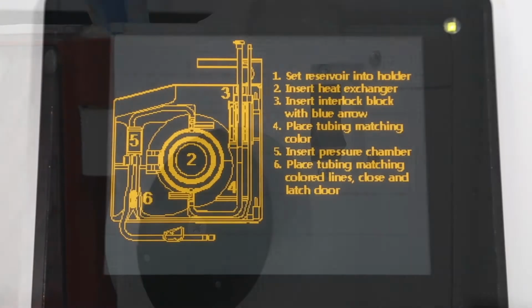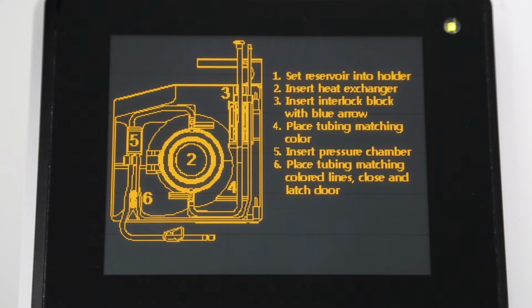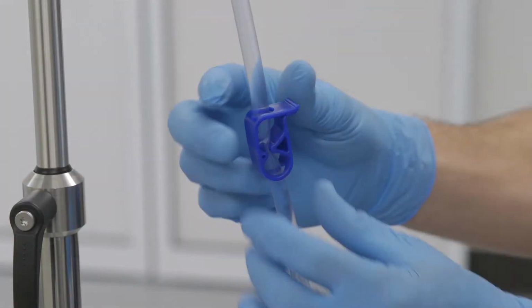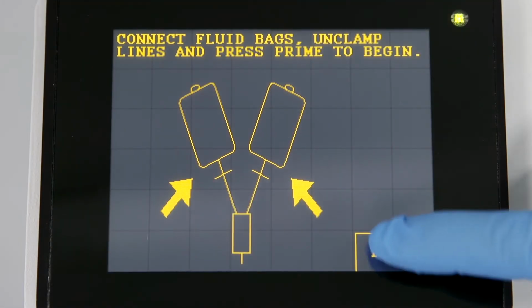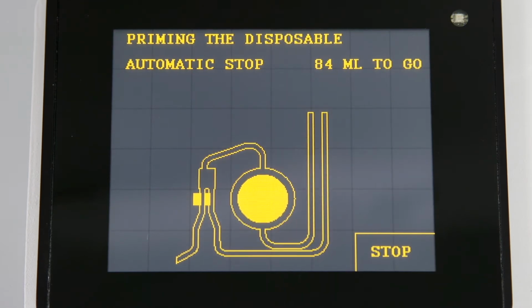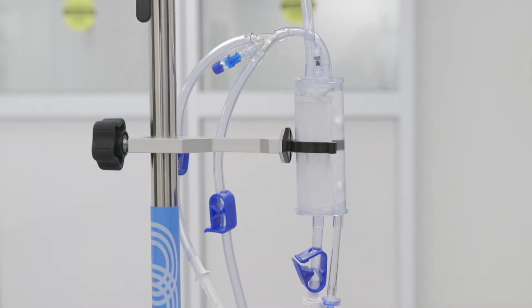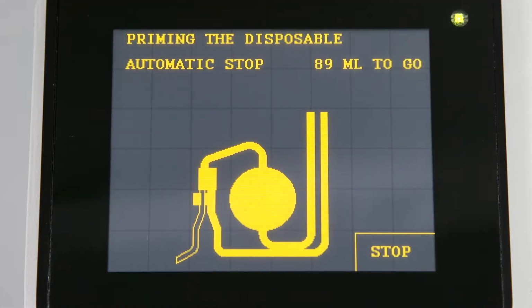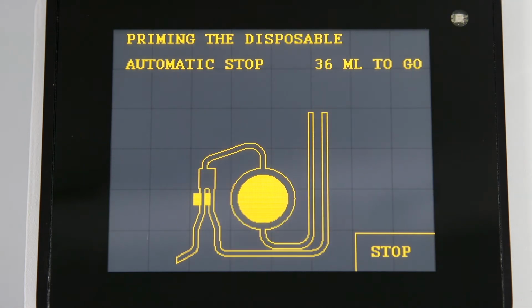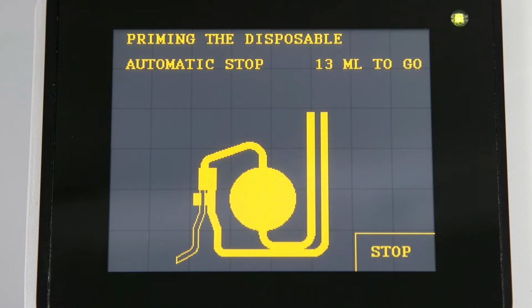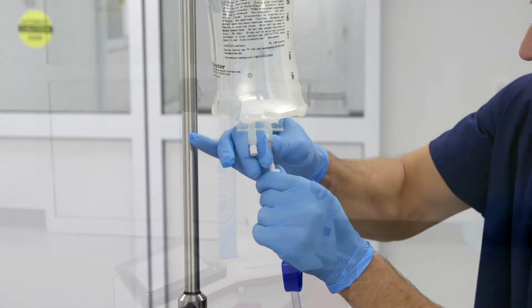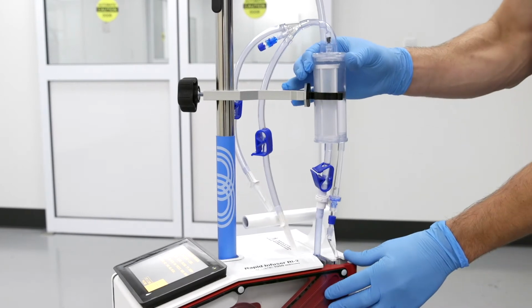When first switched on, the screen will display instructions for installing the disposable set. Press Next to move to the prime screen. You will now be instructed to connect fluid bags and unclamp lines. When ready, press Prime to begin priming the disposable circuit. The roller pump will automatically prime the system in about 13 seconds. Fluid will be drawn through the tubing while the air will be directed out through the recirculation and vent line. During prime, the 100 milliliters to go will count down to 0. If the Belmont Rapid Infuser RI-2 does not count down or resets back to 100 mLs, confirm that there is enough fluid in the system and that the tubing is not kinked or stretched too tight.